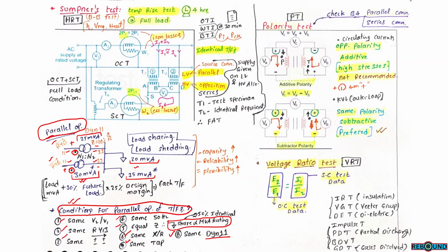And same frequency, as our supply voltage is 50 Hz. So both transformers will operate on 50 Hz frequency only. And same impedance. Here the transformer impedance is 10% and X by R ratio. The same impedance and same X by R ratio must be maintained for the new transformer, and same vector group also.